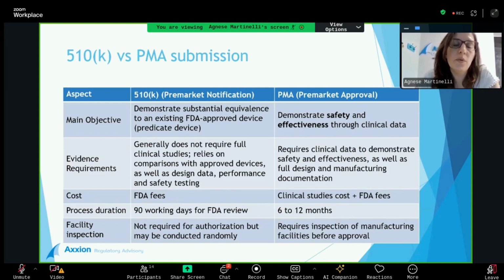In this chart, we would like to share some of the main differences between the 510K and the PMA submission, which we mentioned before is the normal procedure according to the classification of the devices. The main objective of a 510K submission is to demonstrate substantial equivalence to an existing FDA-approved device, normally named the predicate device, while in the PMA we have to demonstrate safety and effectiveness through clinical data.